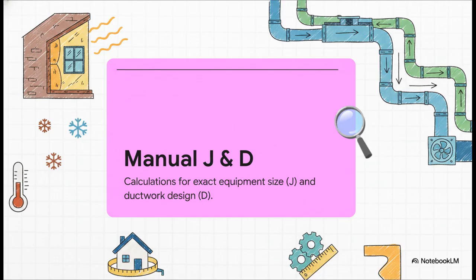Real professionals rely on a standard called Manual J to calculate your exact equipment capacity based on the true heat load. That means factoring in things like your windows, your insulation, and even your sun exposure. Then they pair that with Manual D, which maps out the standards for proper ductwork design, making sure the air actually flows perfectly without any weird restrictions.